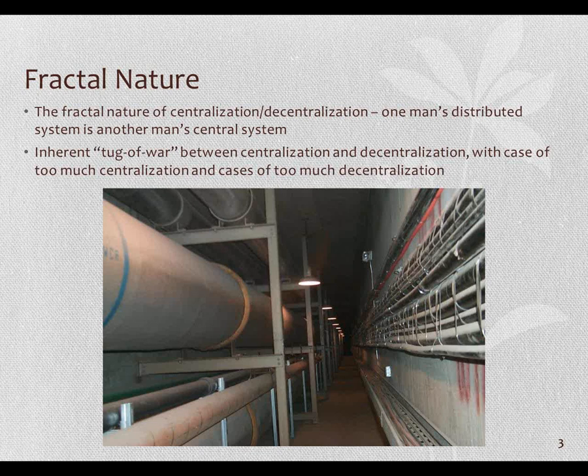For that building, the chiller plant is the central plant, because you could have individual package units for various zones instead. So we have a central plant in the building. But if we zoom out to the campus level, we wouldn't call that building's chiller plant a central plant anymore. We'd consider it a distributed plant, because the campus has its own central plant.